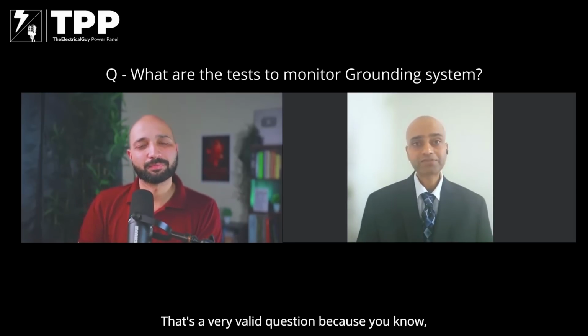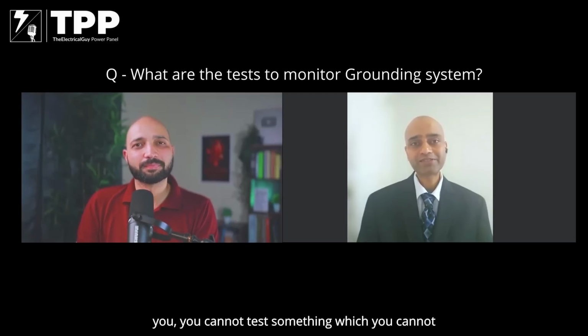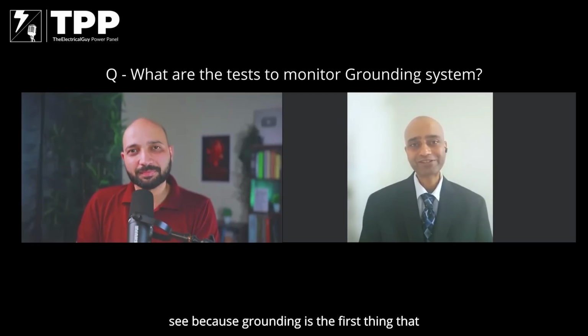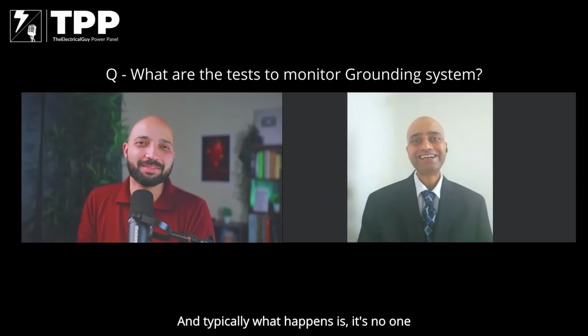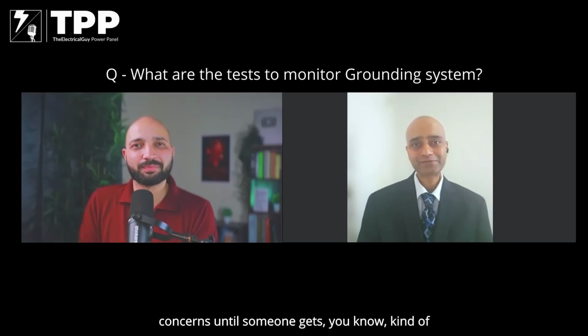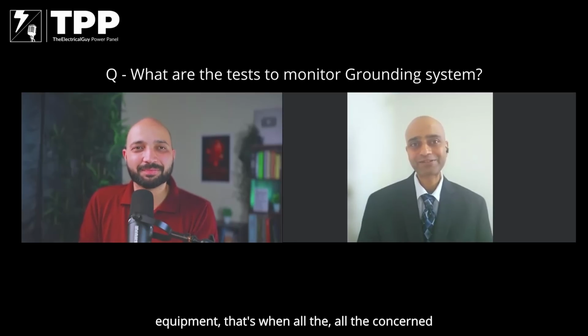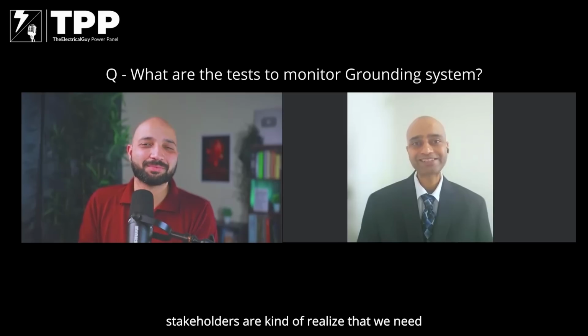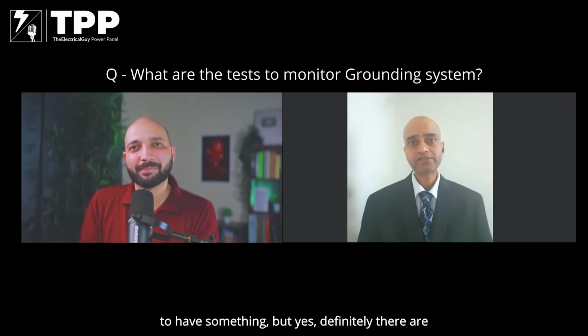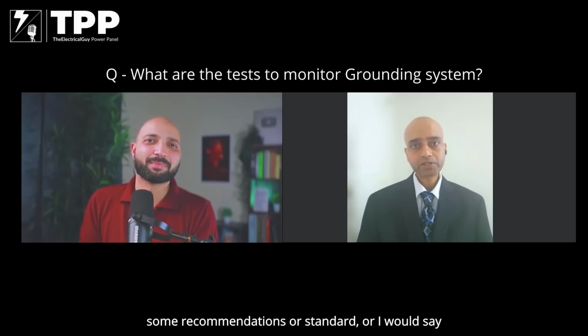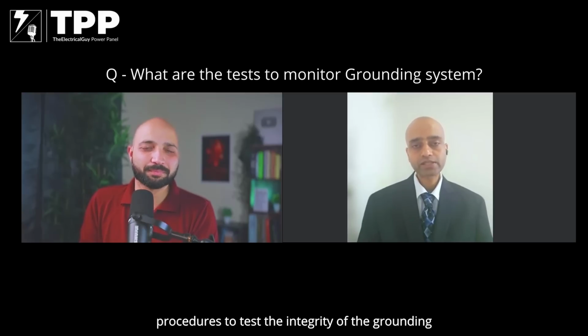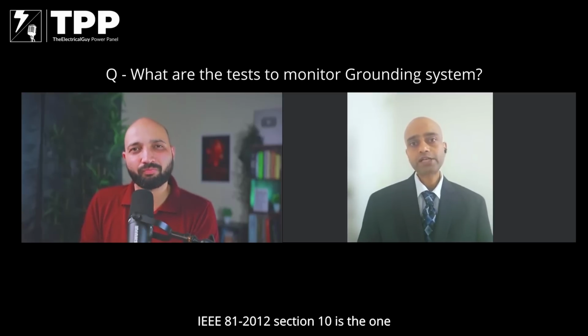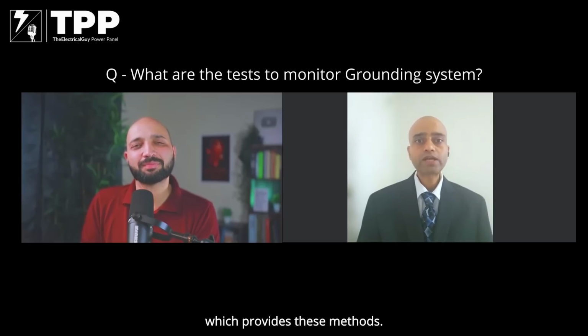That's a very valid question, because you cannot test something which you cannot see—grounding is the first thing that goes in the ground. Typically, no one is concerned until someone gets a sensation at the fence or some other equipment. That's when stakeholders realize something needs to be done. But there are recommendations and standard procedures to test the integrity of the grounding system—IEEE 81 2012 Section 10 provides these methods.